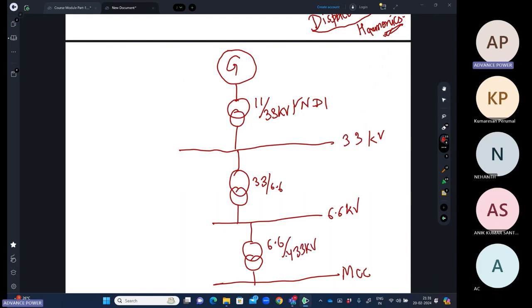All the motor loads will be connected through this MCC. Some HT motors will be connected through the 6.6 kV board. Then there will be transformers of different ratings. So basically the approach will be that we will discuss the motor, which is the first part, or the starting part, of the single line diagram.